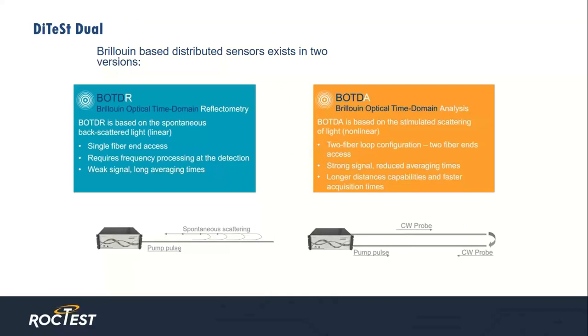The DiTest Dual version, the BOTDA and BOTDR mode, allows reading in both loop and single-ended mode. The BOTDR technique relies on spontaneous Brillouin scattering, where the original optical pulse interacts and scatters back spontaneously within the fiber. The technique uses a single fiber end access, with the particular advantage that in case of cable breakage, for example when the cable is already installed or buried in the soil, it is possible to resume the total cable length by measuring via the opposite direction of the cable loop setup.